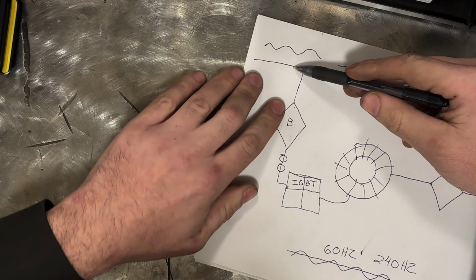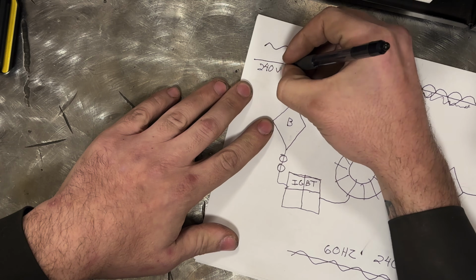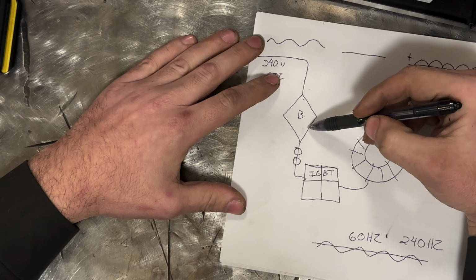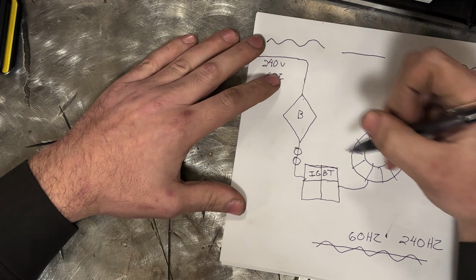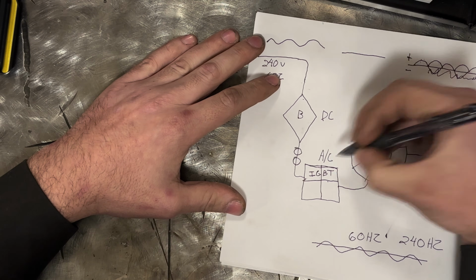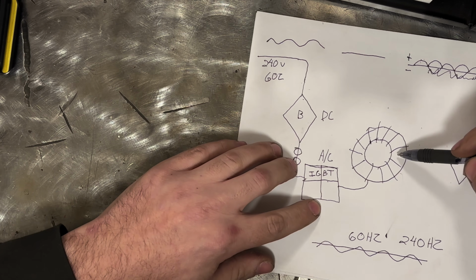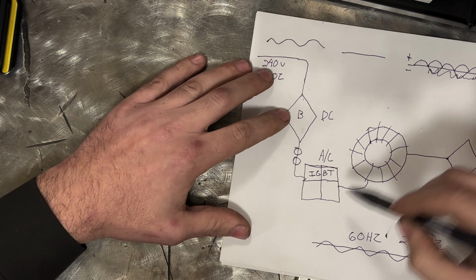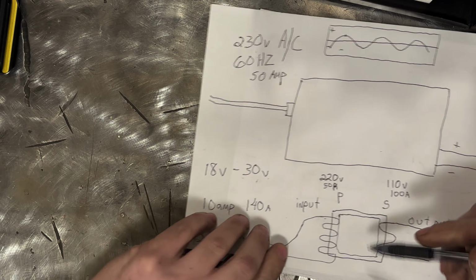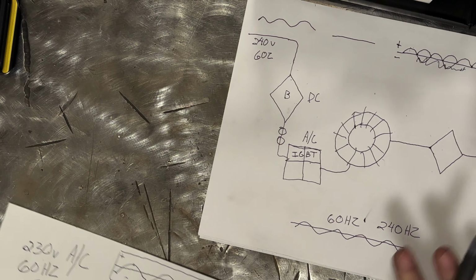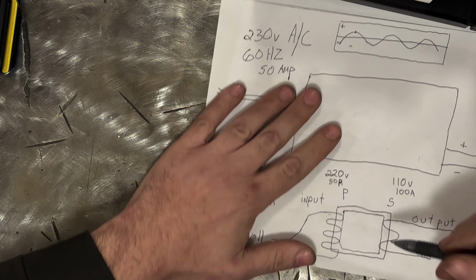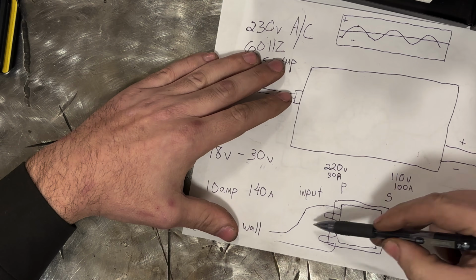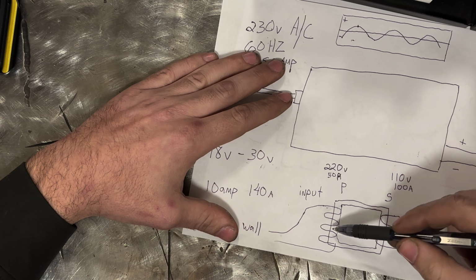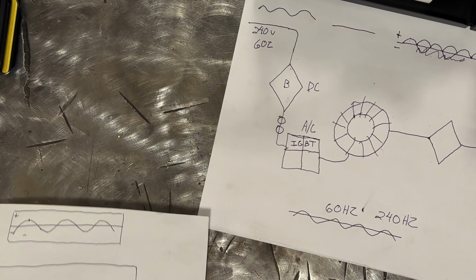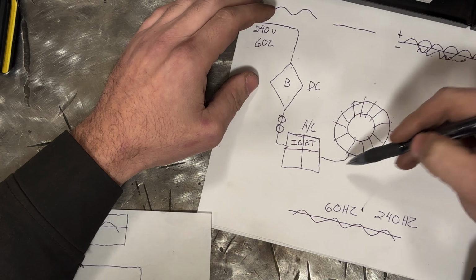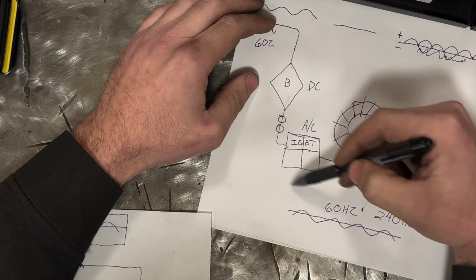Now, to go back here, like I said, you're starting at 240 volt, 60 hertz. You're converting it to DC, then you're converting it back to AC. And the reason is that transformers do not work on DC. They need a change in the magnetic field, like on this description, to impart an electromotive force, I believe it's called, on the other side of the transformer. So without alternating, there is no change in flux, there is no change in magnetic field, therefore there is no change in the output. So you can't have this transformer function on DC, which is why you need this.